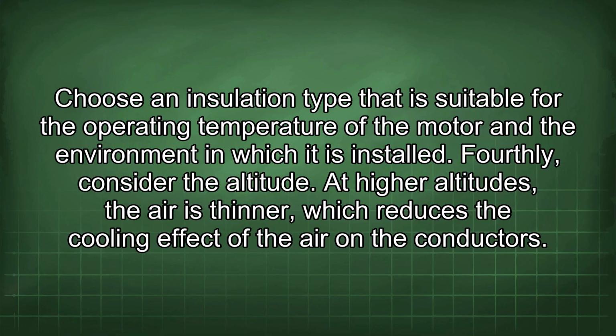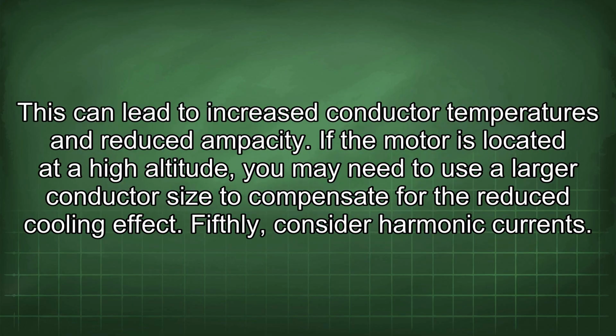At higher altitudes, the air is thinner, which reduces the cooling effect of the air on the conductors. This can lead to increased conductor temperatures and reduced ampacity. If the motor is located at a high altitude, you may need to use a larger conductor size to compensate for the reduced cooling effect.